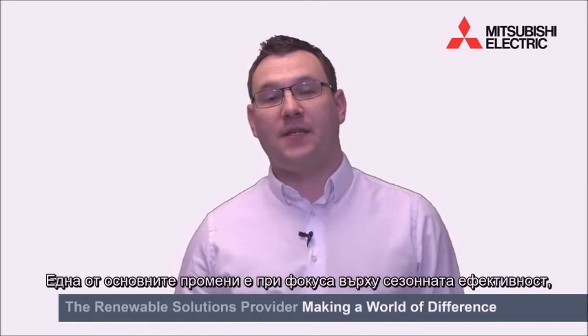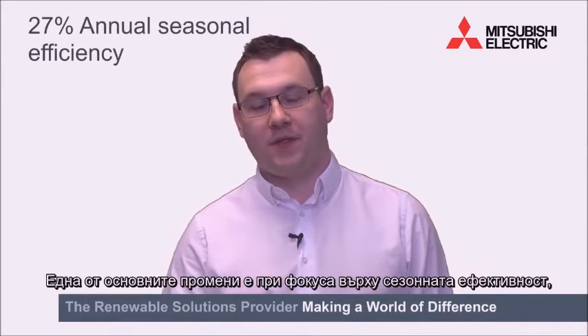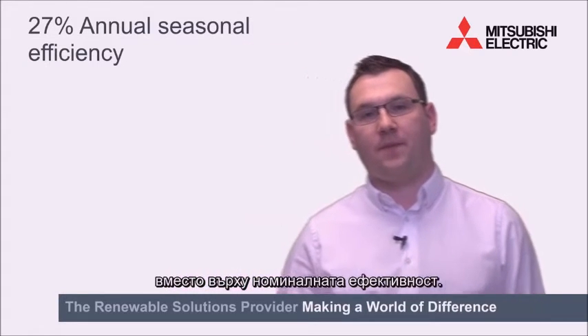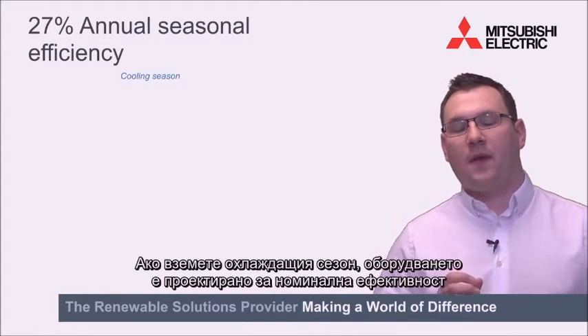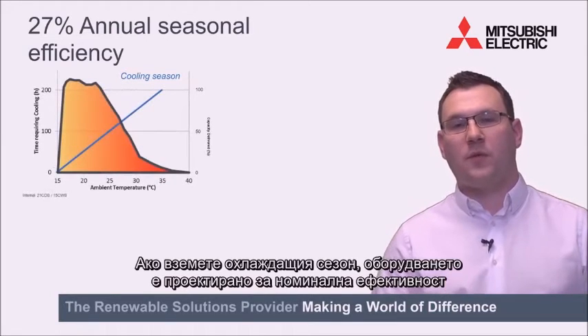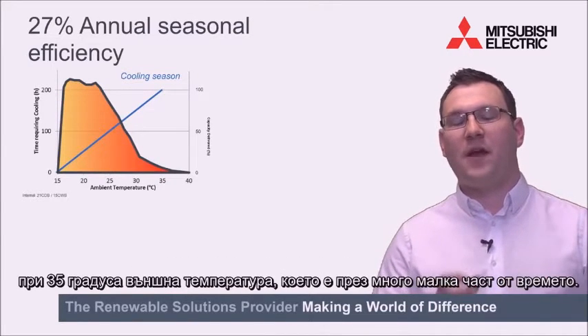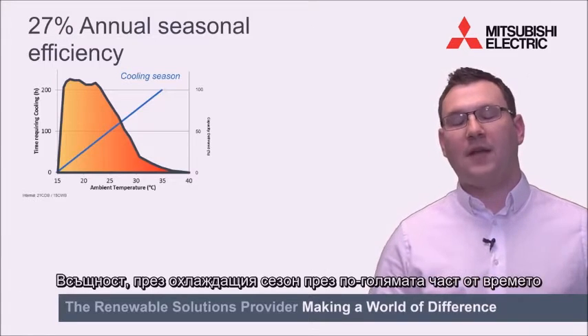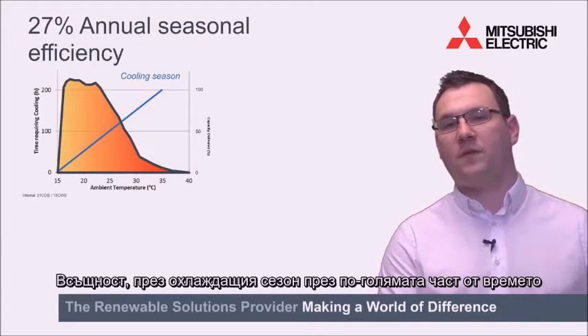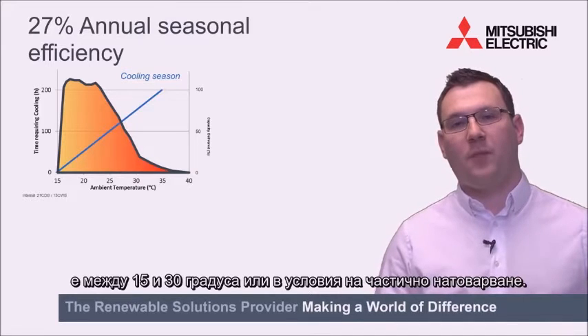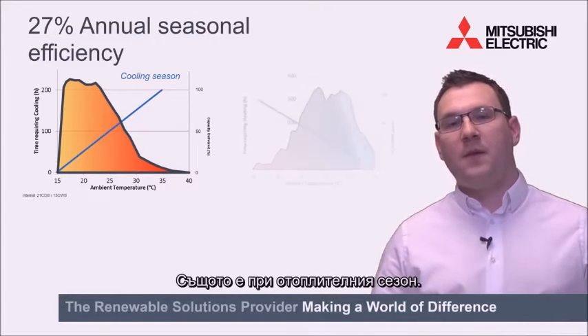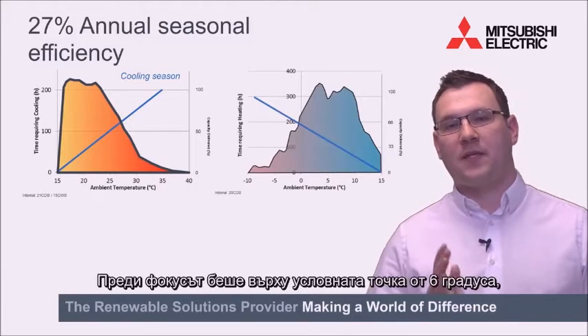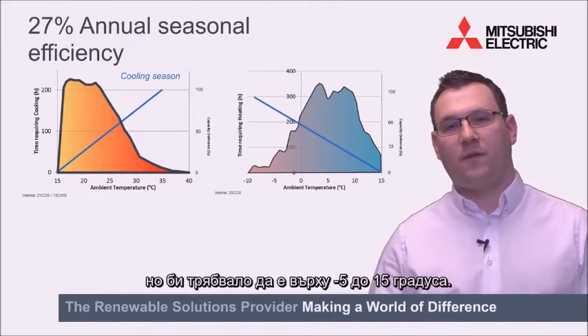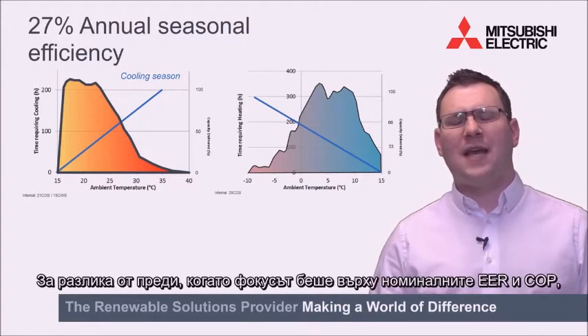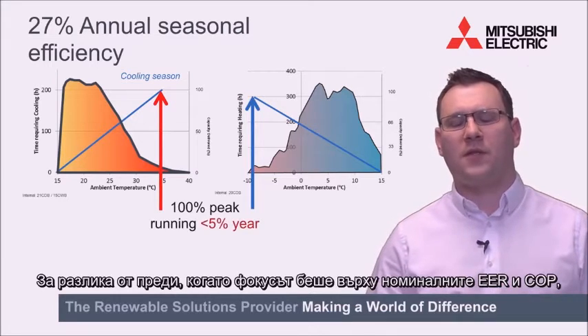One of the key design changes is around the focus towards seasonal efficiency against nominal efficiency. If you look at the cooling season, 35-degree ambient is where equipment was designed for nominal efficiency, and there's very little time spent at this point. Actually, in the cooling season, the majority of time is spent between 15 and 30 degrees, or in the partial load condition. The same thing is on the heating season. Previously a spot condition at 6 degrees, but actually the focus should be around the rest of the year between -5 up to 15. So gone are the days when we focus on that nominal EER and COP.